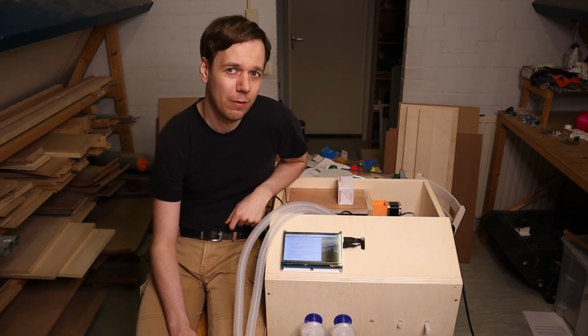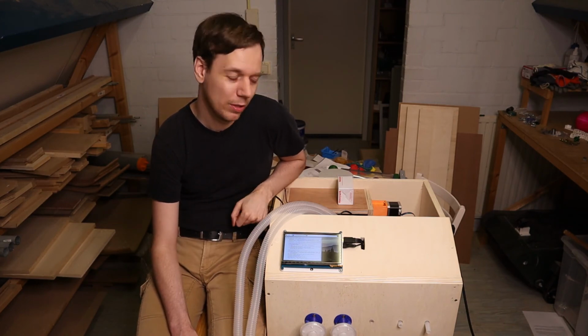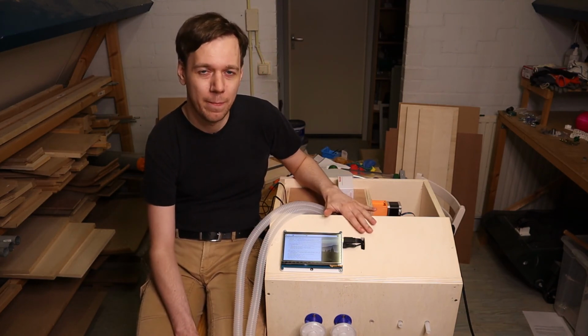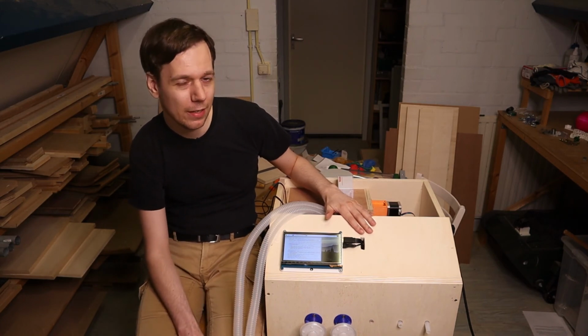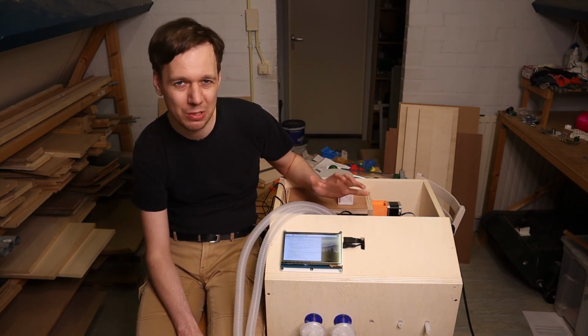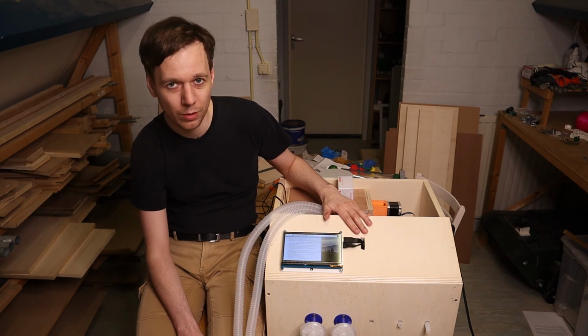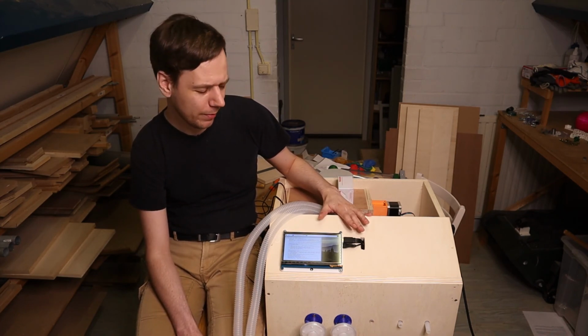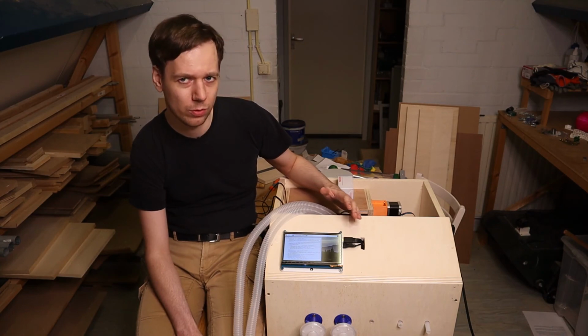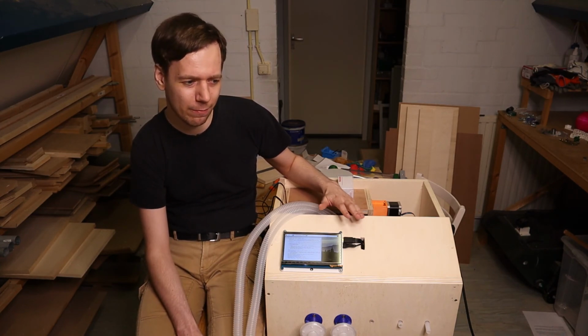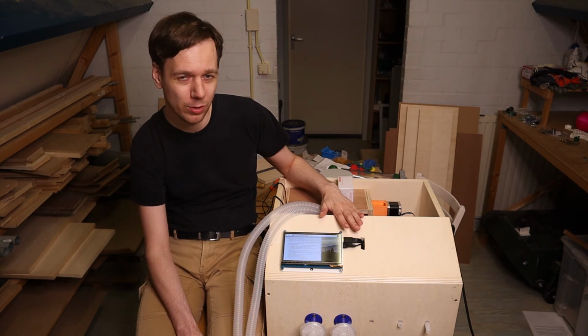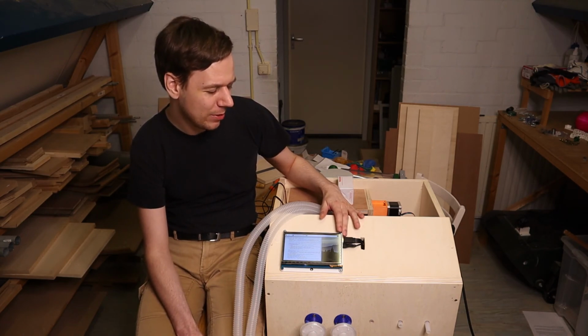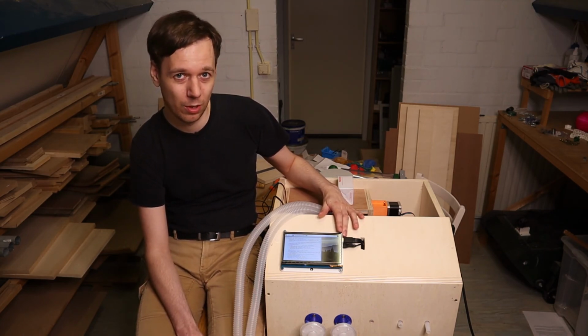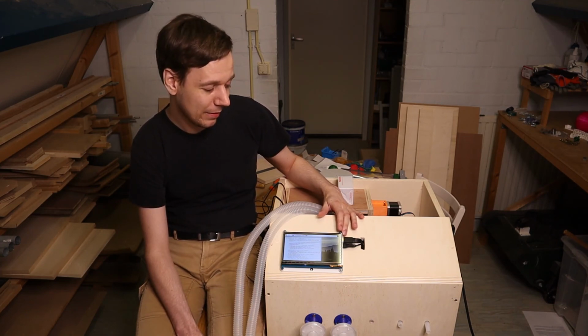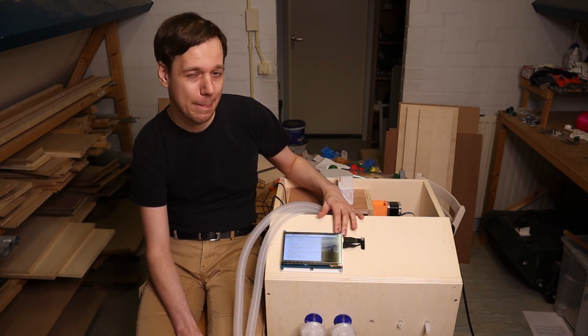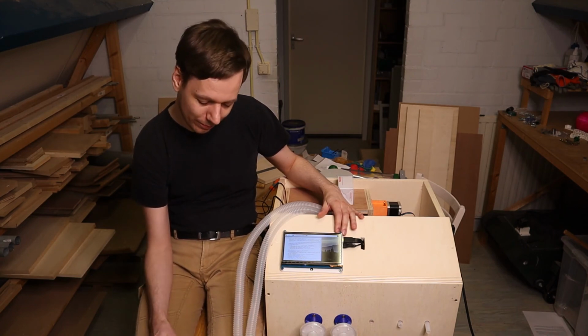The other thing, which is fairly simple, is an overpressure release valve, which this thing currently doesn't have. So if for any reason at any point the pressure goes above 60 to 80 centimeters of water, that should be blown off immediately. If you go above that, you risk inflicting acute barotrauma on your patient, which basically means that you're severely injuring his lungs by blowing them up. If you're already suffering from COVID, that's really not a great outlook.